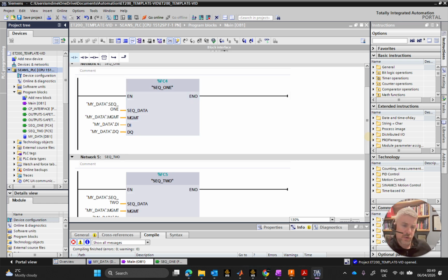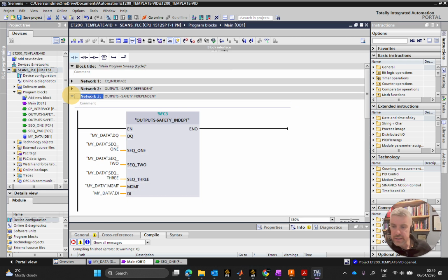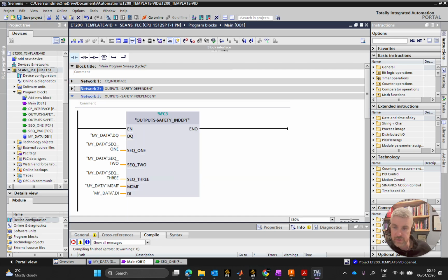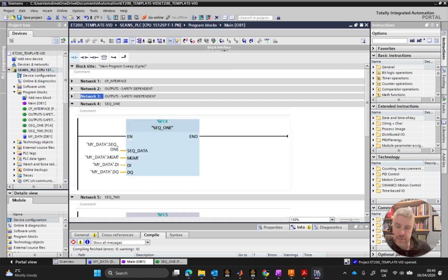Now the one thing I'm going to do before we finish this up is, in the same vein as where we have put in conditions to move into some of these functions, I'm going to put in the same sort of conditions here for sequence 1. I do not want to scan this block at all unless I'm running sequence 1, and particularly maybe that I'm in a run mode, but I'll discuss modes again at another time. So let's do a comparator operation.